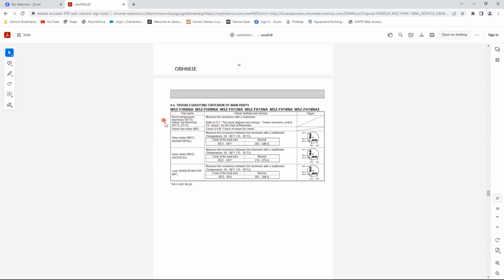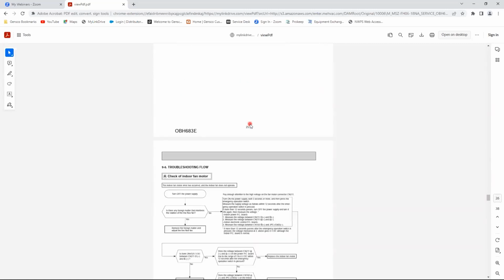So if you do not have a maintenance tool set up where you can plug in and see all of your thermistor values on your computer screen, well, if you have to go stand on the back of the customer's couch and take the indoor head apart to get to the thermistor connections, you can come here and it will tell you, refer to 9-7 test point diagram and voltage. And we're going to scroll down to that.